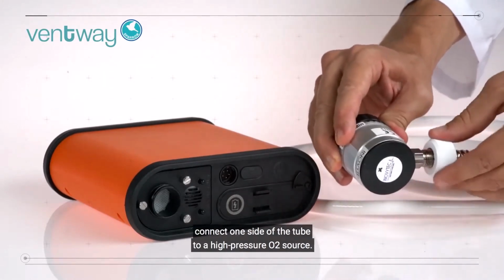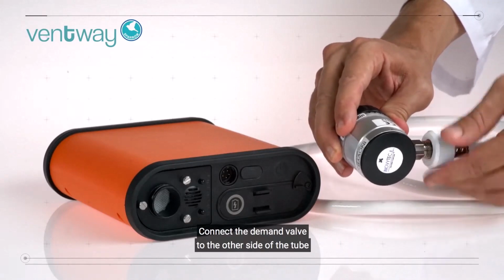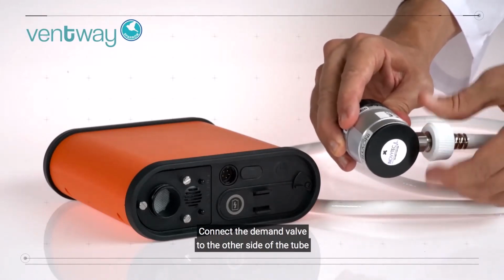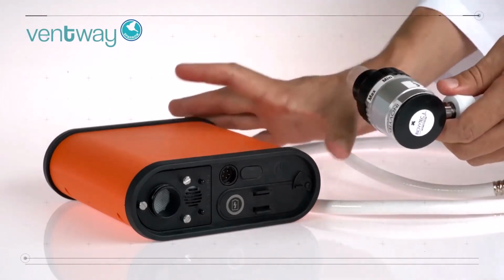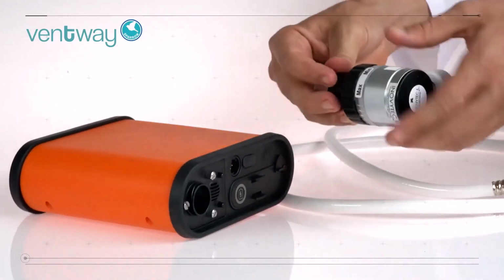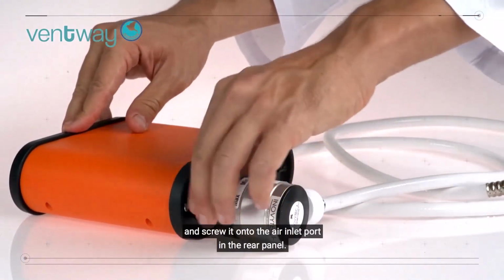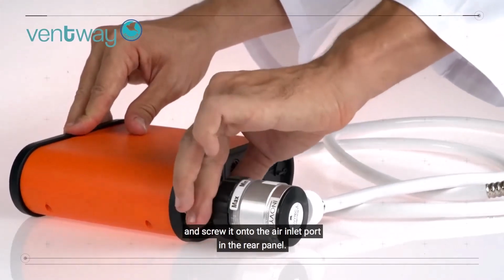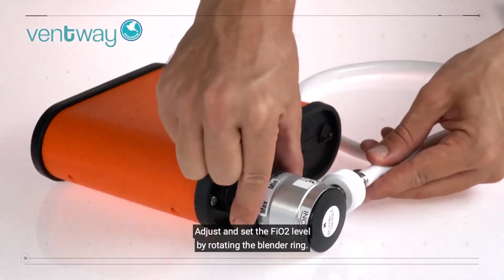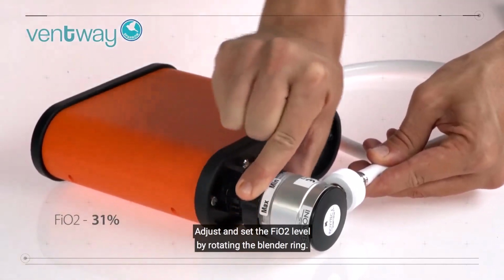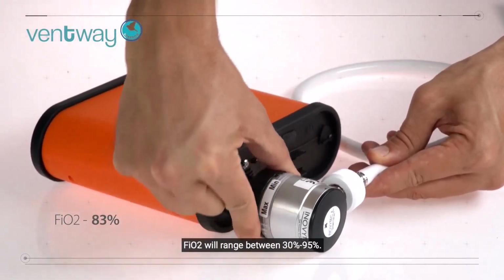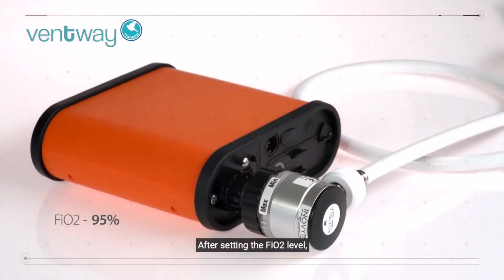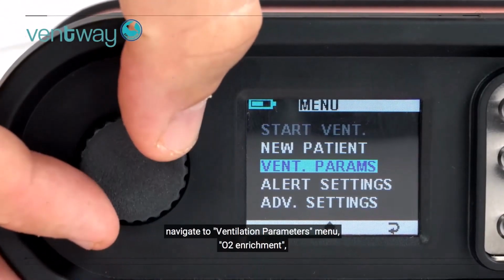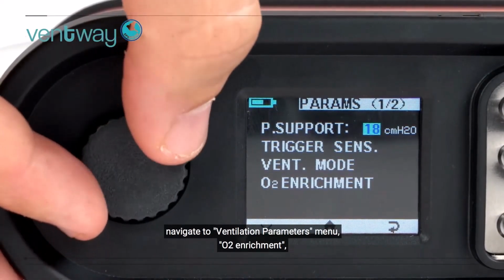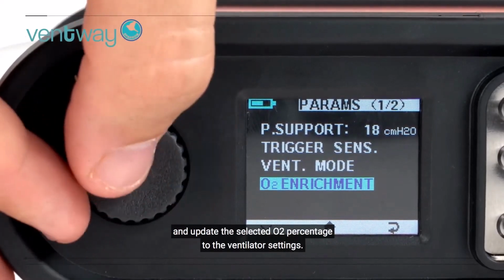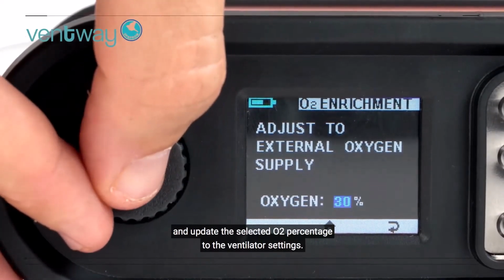Connect one side of the tube to a high-pressure O2 source. Connect the demand valve to the other side of the tube. And screw it onto the air inlet port in the rear panel. Adjust and set the FiO2 level by rotating the blender ring. FiO2 will range between 30 and 95%. After setting the FiO2 level, navigate to Ventilation Parameters menu, O2 Enrichment, and update the selected O2 percentage to the ventilator settings.